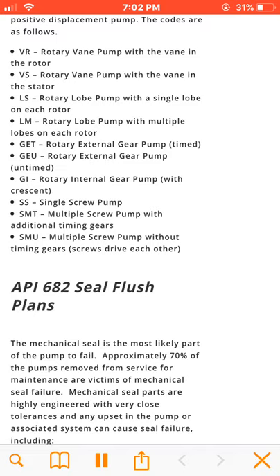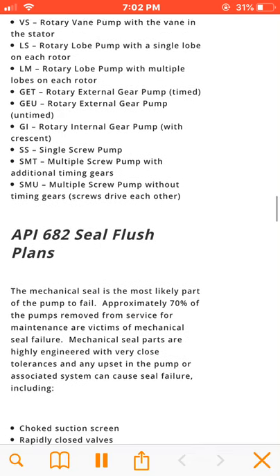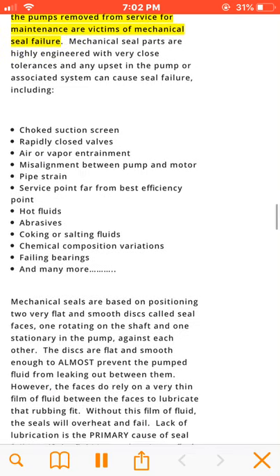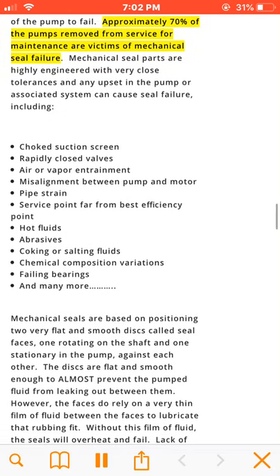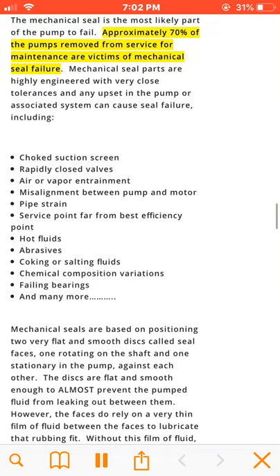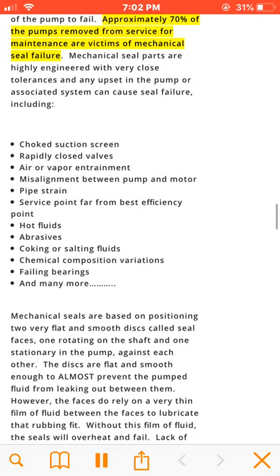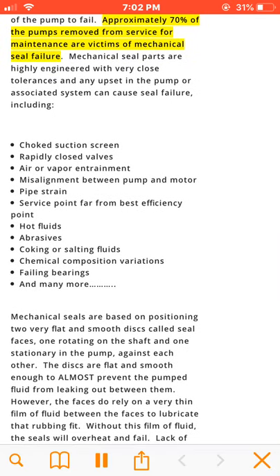The mechanical seal is the most likely part of the pump to fail. Approximately 70% of the pumps removed from service for maintenance are victims of mechanical seal failure. Mechanical seal parts are highly engineered with very close tolerances, and any upset in the pump or associated system can cause seal failure, including the following causes.